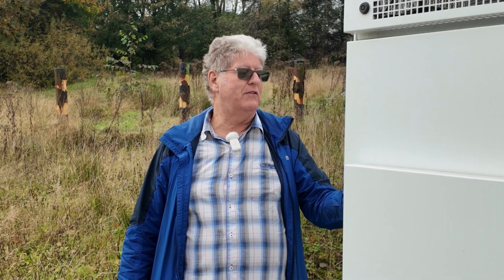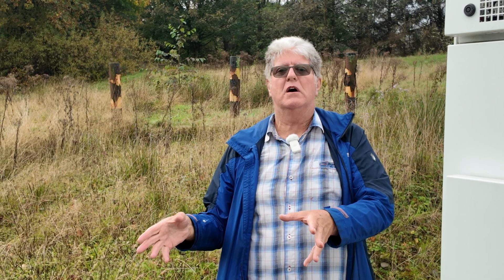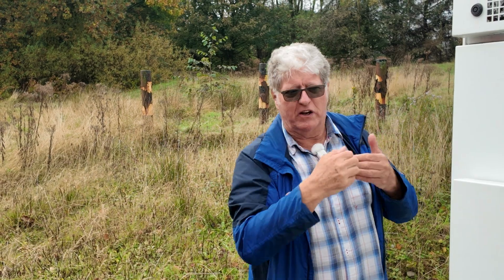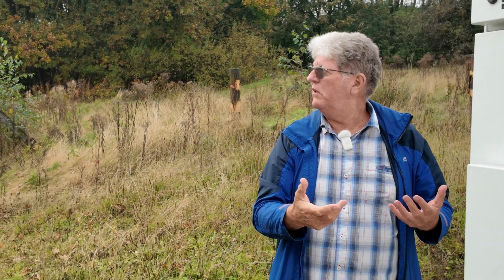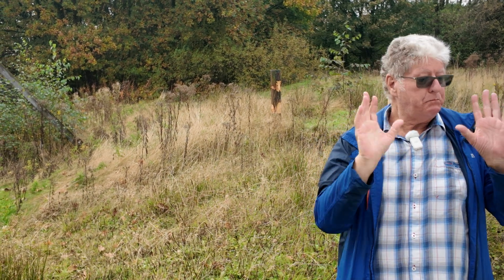So we've got plenty of power in each of these cabinets to power four of the V3 chargers over there. And as I said before, they share power between them — there's a common bus, a voltage bus between them, and they can shift power between cabinets. So it means if everyone piles into one or two cabinets' worth — if eight chargers get filled up and everyone's charging at maximum rate — the third cabinet, which isn't charging anything, can share power between them.